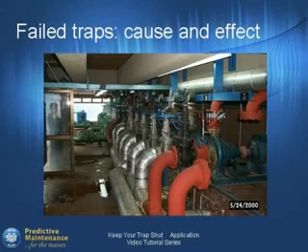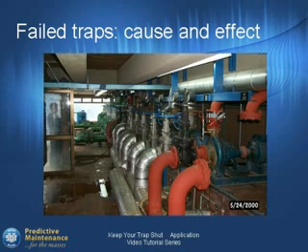Steam traps are necessary for the overall efficiency of heat energy transfer. When traps fail, they waste money. They create back pressure in the steam system and cause process failures or quality issues with your end product. If condensate is not removed from the system, it can pool in low areas of piping. Eventually the pool grows in size until it closes the pipe completely, causing back pressure and water hammer.